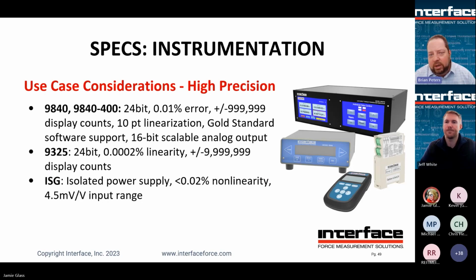If you need a DIN rail or a signal conditioner that's small and easy to mount, our ISG DIN rail happens to be a very nice option in that it has an isolated ground and isolated power supply from the sensor side. Remember, sensors are ratiometric, so you want to try to keep things clean. Also offers good nonlinearity, and it still accommodates a wide input range up to 4.5 millivolt per volt. Remember, I mentioned that earlier. Pay close attention when you're choosing instrumentation that it can accommodate. A lot of Interface load cells being 4 millivolt per volt, customers have run into issues because a lot of sensors are only 2 or 3. So because we offer that 4, and if you're using something that's 4, make sure that you've got the ability to take full advantage of the additional signal and use it to full scale.